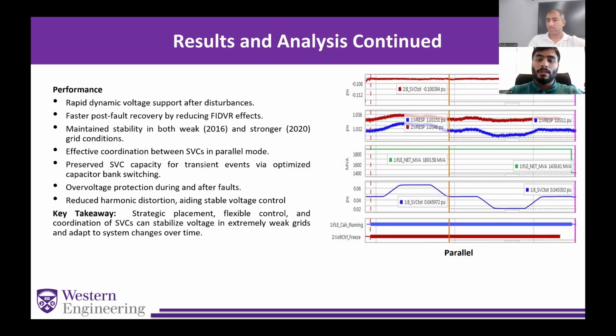So if you look at the bottom red line graph, it shows that the second SVC freezes its voltage control capacity when the first SVC is calculating the fault or doing an analysis on the system voltage. So due to this interconnection of two SVCs and the installation of the SVCs, the system became strong from a weak system, and they upgraded the system to cater to the issue of high load over there. Can you go to the next slide, please?